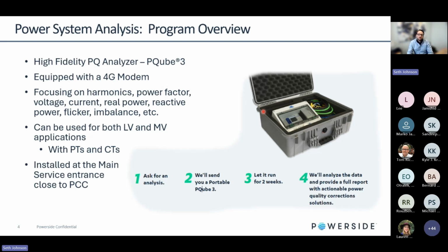And this is really important for this program because as we send these out into the field, we're actually able to connect up to them remotely from basically anywhere in the world, which is fantastic. One of the age-old problems with power system studies is getting a measurement device installed and making sure that it's installed correctly. We see data oftentimes from customers that will give us power quality data, and we quickly realize that the CT was reversed or it wasn't connected properly, and then they have to rerun the study. And so that's a really big added benefit to this program, is the ability to remotely connect up to the portable device as it's installed at the customer facility.